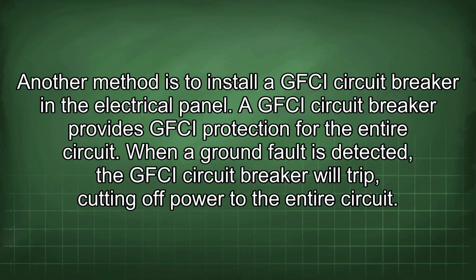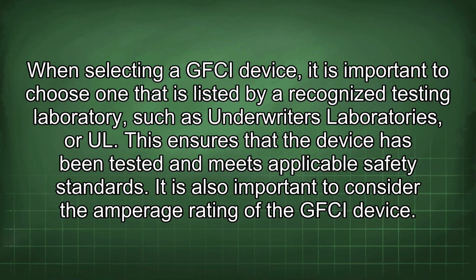Another method is to install a GFCI circuit breaker in the electrical panel. A GFCI circuit breaker provides GFCI protection for the entire circuit. When a ground fault is detected, the GFCI circuit breaker will trip, cutting off power to the entire circuit. When selecting a GFCI device, it is important to choose one that is listed by a recognized testing laboratory, such as Underwriters Laboratories. This ensures that the device has been tested and meets applicable safety standards.